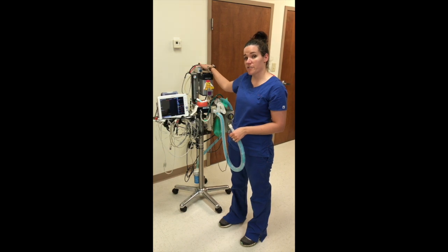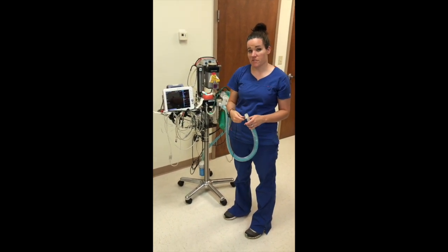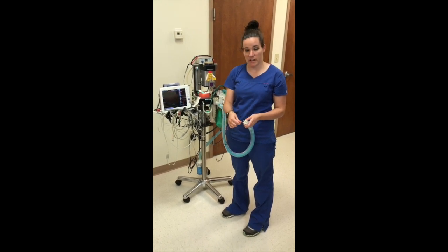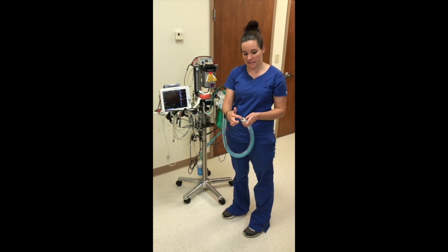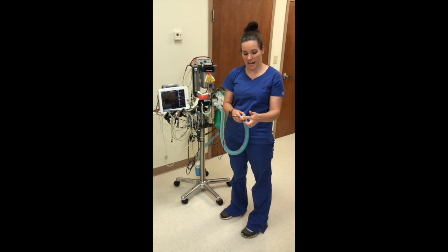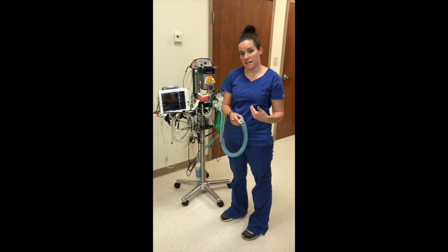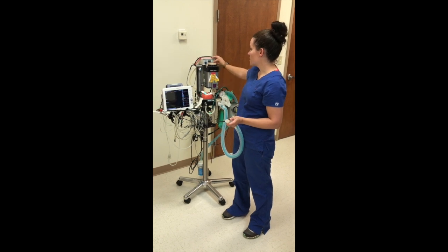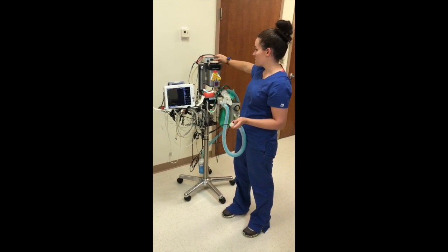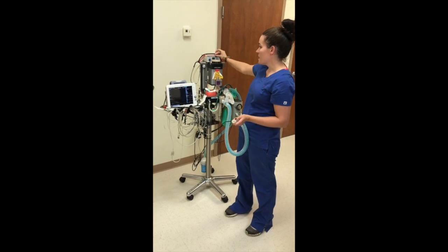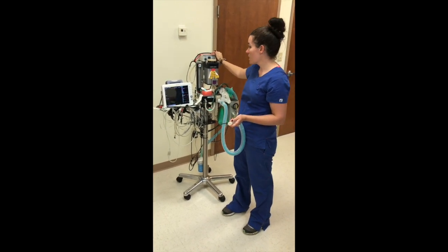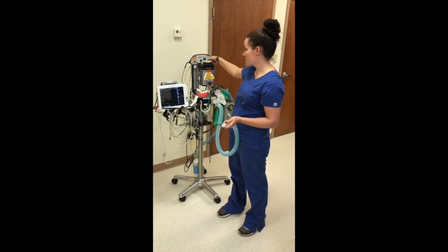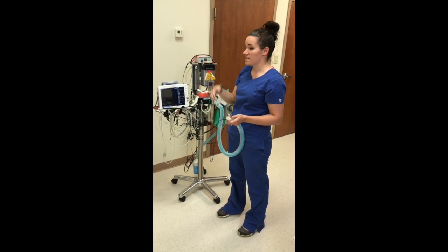This is our respiratory monitor, so we have an apnea alarm that alerts us if the patient has not taken a breath in a preset time frame. So we have a sensor here that goes on the end of our rebreathing tube, and it has a sensor that hangs out in the middle here that is going to sense as the air passes due to inhalation and exhalation. And then this timer counts up. When it gets to the preset time, in this case 20 seconds, it will beep to let us know that the patient has not taken a breath. We can adjust this to various levels. As a standard, we have it on every 20 seconds, but we can adjust it if needed based on the patient.